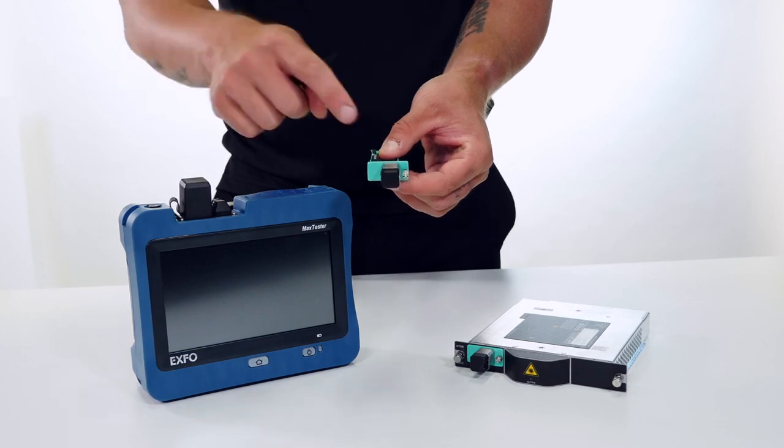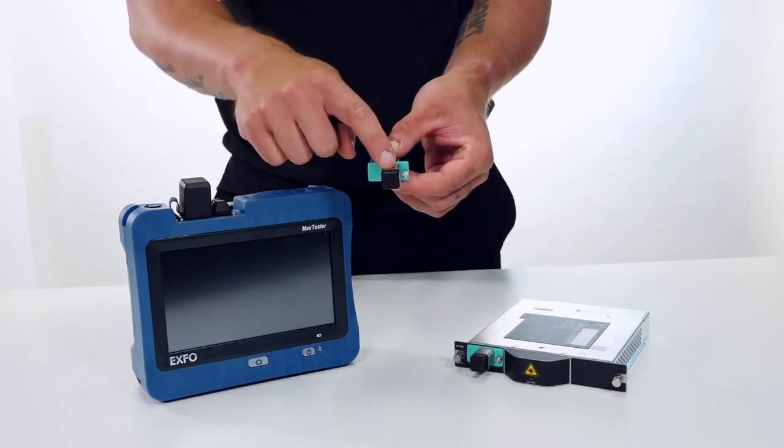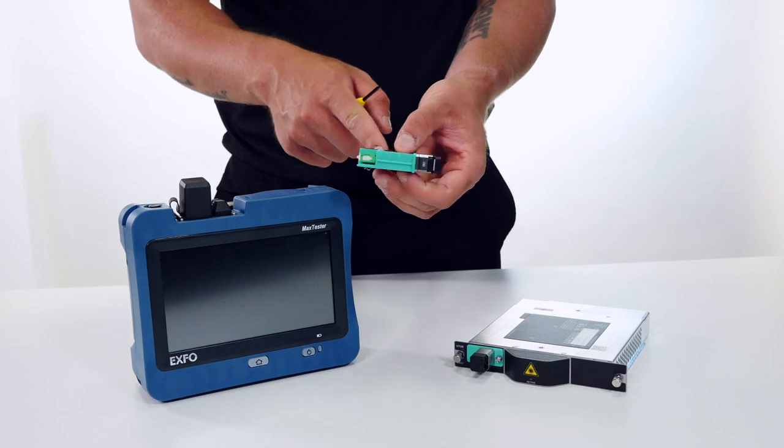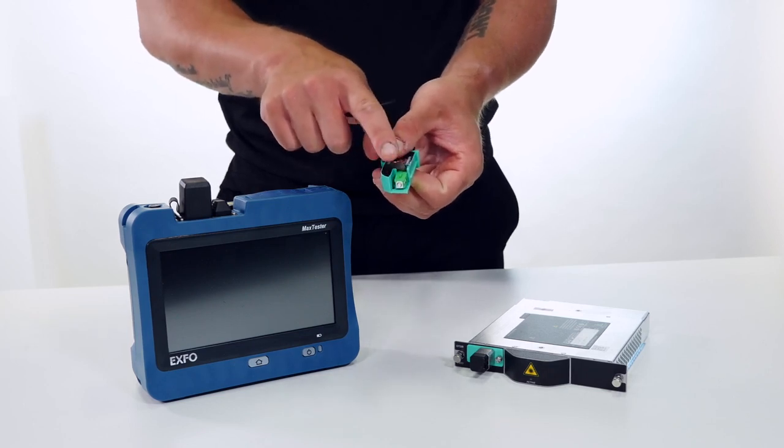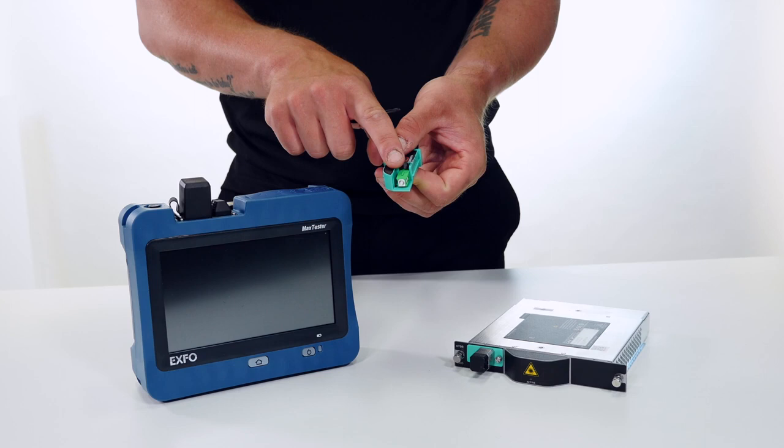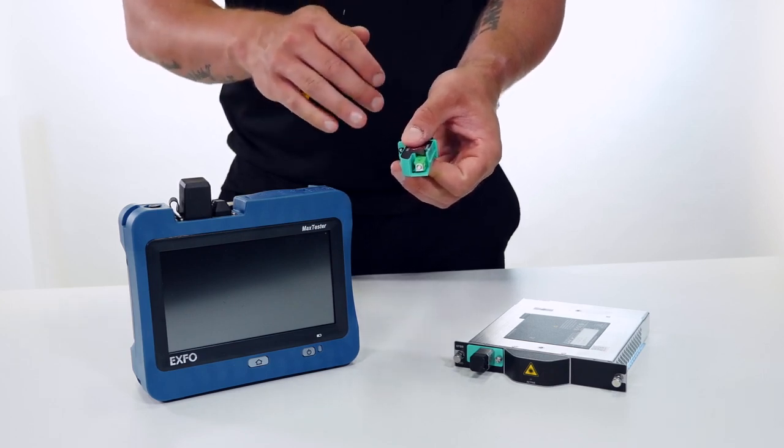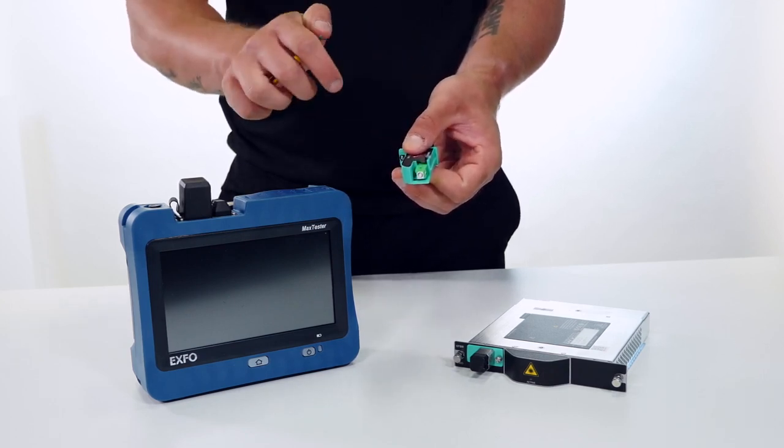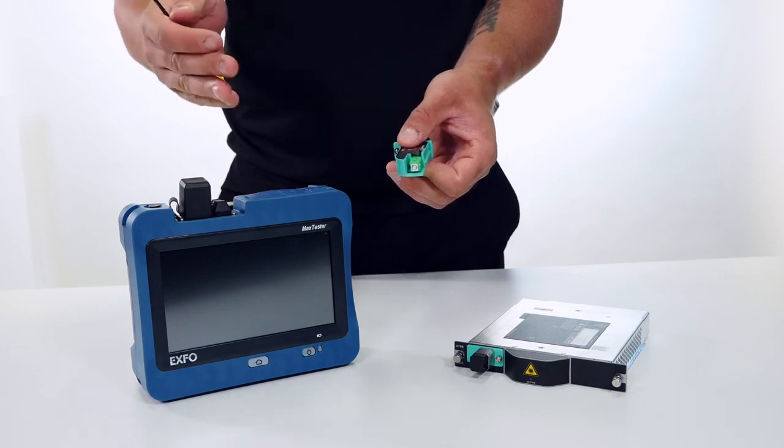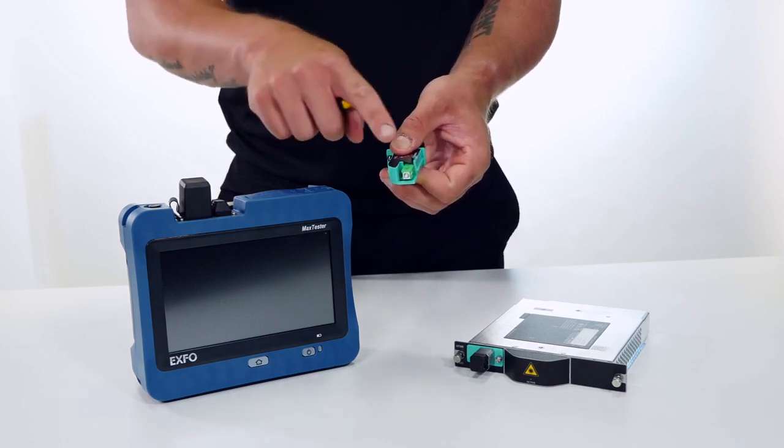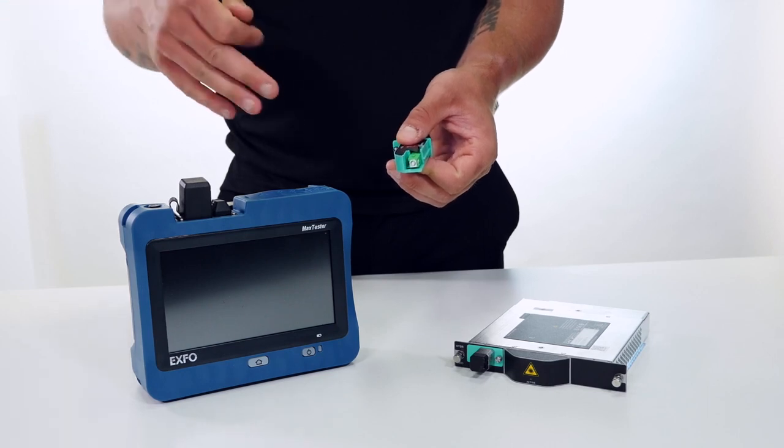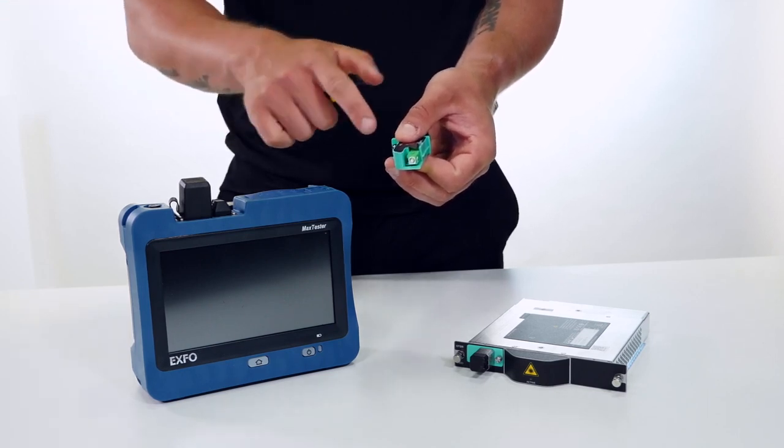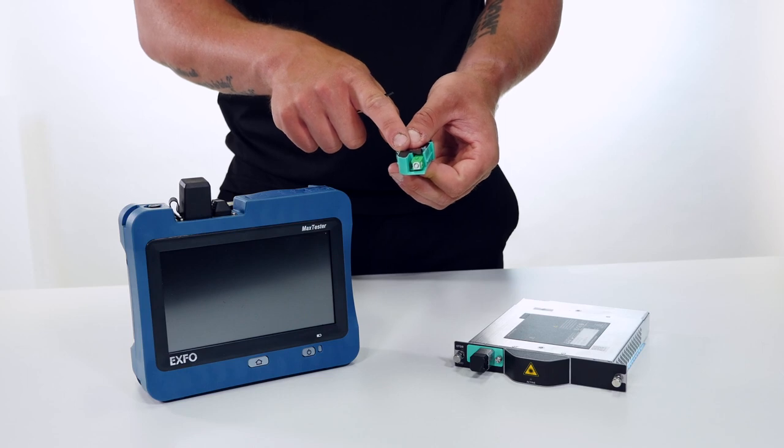So we can change the connector itself and it's going to minimize the number of connections on the internal connector which is where the calibration is done. If we change the swap out connector we do not change the calibration date. So it's not reset, it's not nullified. If I have to calibrate my internal connector in six months, I still have to calibrate in six months even if I've changed my connector itself.